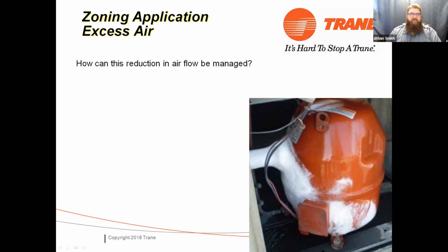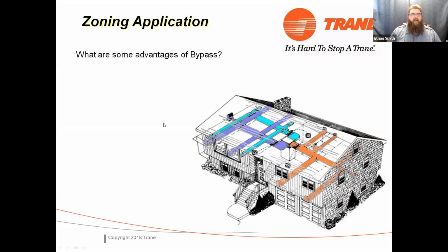There's lots of different ways to do it. Some of them will have a managed bypass where it actually has a position sensitive motor. They can open it a little or a lot. Others will just have what's called a barometric bypass, which is a fancy damper with a weight on an arm that you can calibrate, with big quotation marks there, to manage your excess air. So bypass is probably the most common. Okay, so let's talk about bypass a little bit, guys. What are some advantages of bypass? Why would you want to use a bypass?